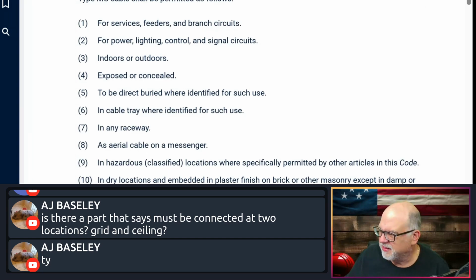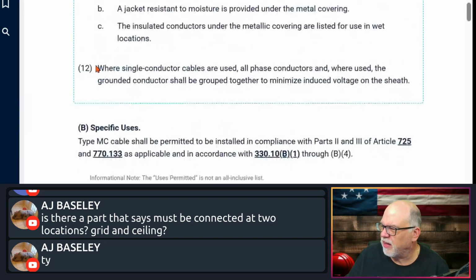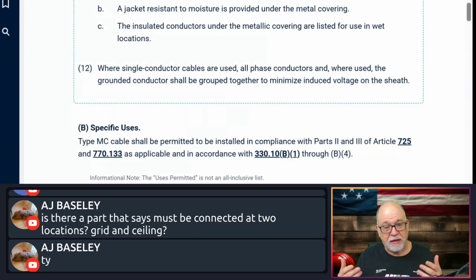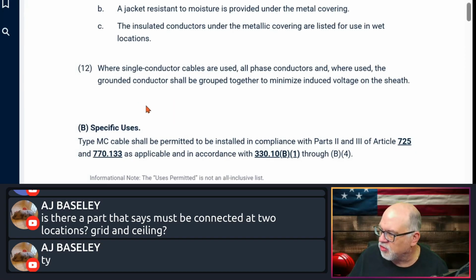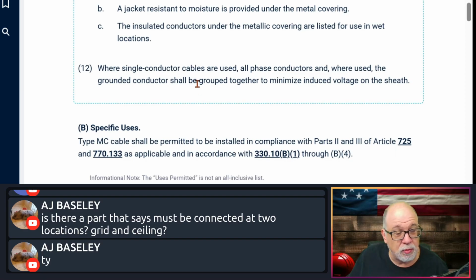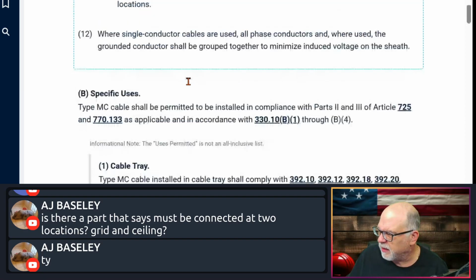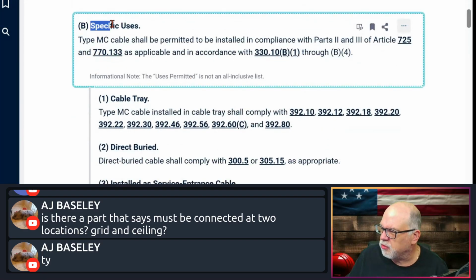So that's the requirement. Again, close proximity, so we don't get a magnetic effect. And obviously this can be magnified if you're taking it through a raceway entry into an enclosure that is a ferrous metal, then you can cause a lot of problems. So there are rules you have to follow for that as well. Just keep that in mind. It's a shame we didn't put a reference to that right here.